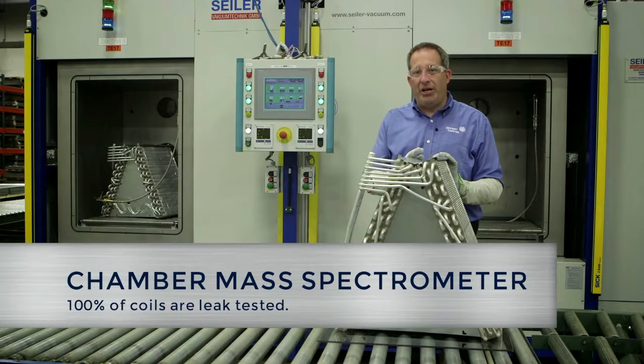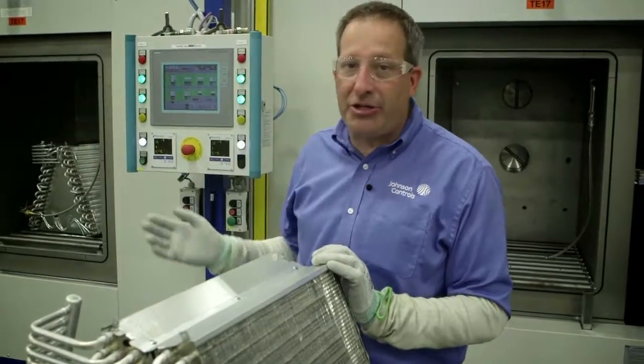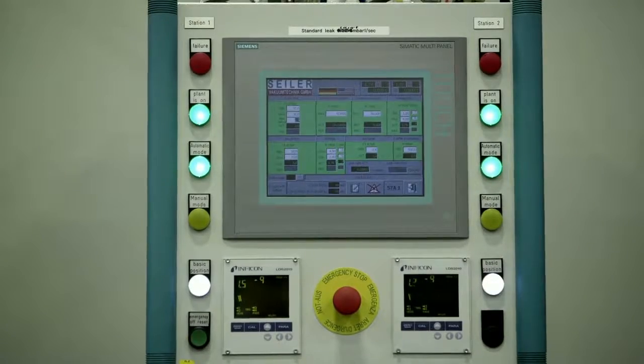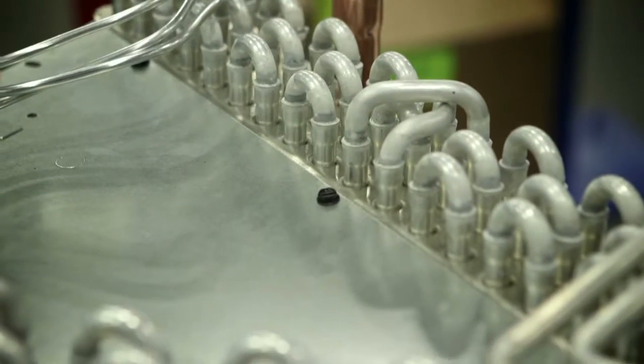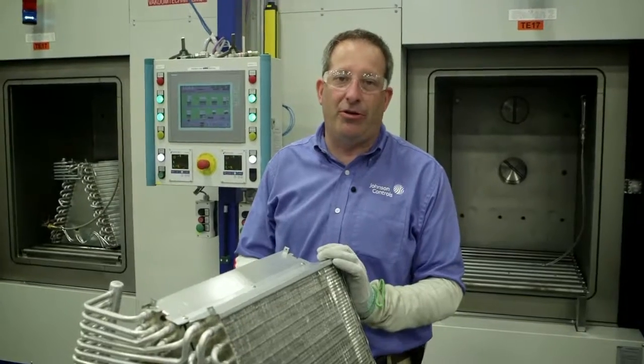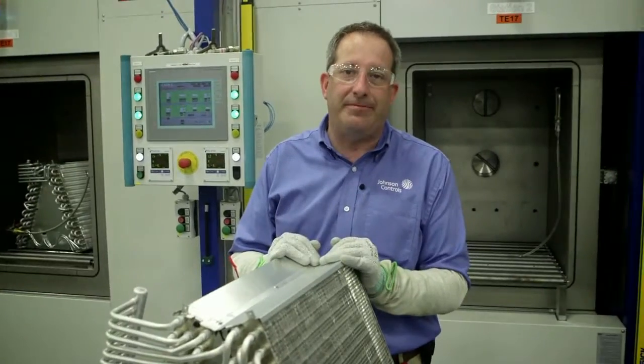Once we've completed all the brazing on this unit, we're going to check it in a chamber helium mass spectrometer. The reason we use a chamber is we want to be able to capture all the leaks that may exist on any of the braze joints. We do this to ensure leak-free operation throughout the life of this unit.